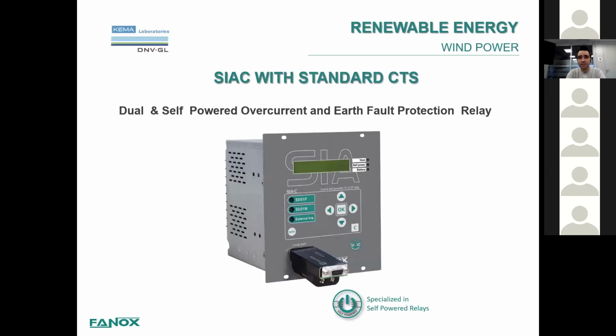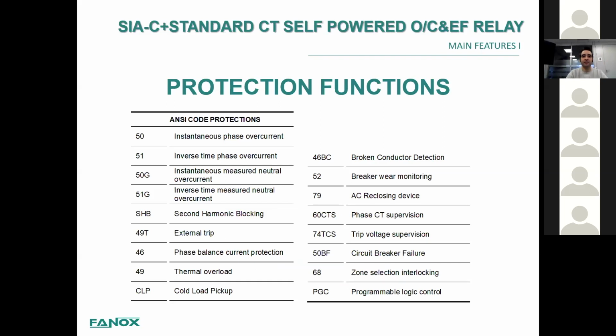This one is the SIA-C relay with the standard CTs. As you see, the shape is different, and the protection functions are much more complex. We also have the phase overcurrents and earth fault overcurrents, external trips, but we also have some more interesting protection functions, like phase balance protections. We have the monitoring of the circuit breaker, function 52, and a reclosing device in case you need to reclose after a trip and, after some time, reconnect the rest of the generator. And we have some control functions like phase CT supervision, trip circuit supervision, and even circuit breaker failure.